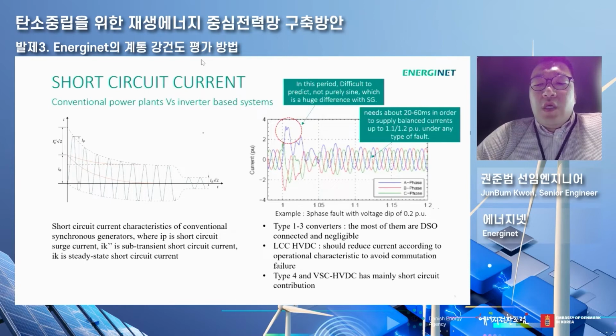So we try to understand whether it can be applied, what the meaning of that is, and which are critical. In the case of type 1 to 3 converters, most of them are DSO connected and negligible. In the case of TSO, it also doesn't have a huge influence, but LCC HVDC should reduce current according to its operational characteristic to avoid commutation failure. Also, type 4 and VSC HVDC have mainly short circuit contribution. So it's a voltage source converter, offshore or PV, you can see that.